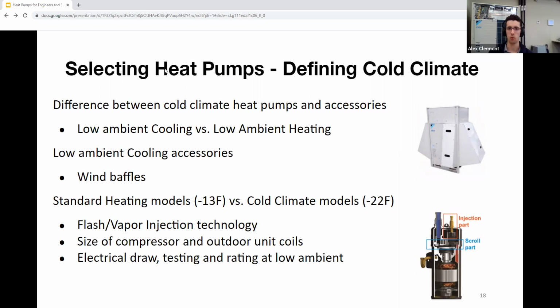So first of all, before we begin, we actually want to define cold climate here in the selecting heat pump section. So what do we mean by cold climate? Oftentimes we see this called out on floor plans by engineers, and we just want to define what that actually means, because it can actually mean quite a lot. There's a big difference between cold climate heating and cold climate cooling. These machines are really good at heating, but they can also be used in cooling applications in the wintertime. But those are two fundamentally different challenges. In low ambient heating, you're actually trying to extract heat from air. And in order to do so effectively, you actually need inverter-driven compressors and vapor injection technologies. The two main points that you need. For low ambient cooling, you're actually trying to condense refrigerant at cold temperatures, which is actually too easy for the machine to do.